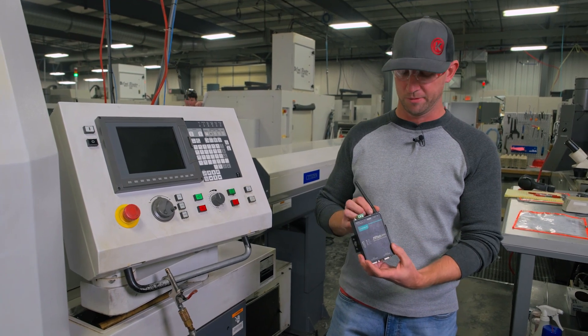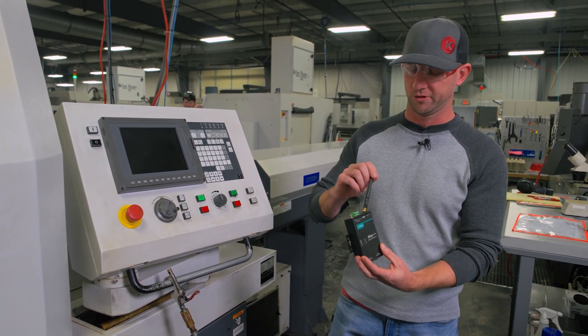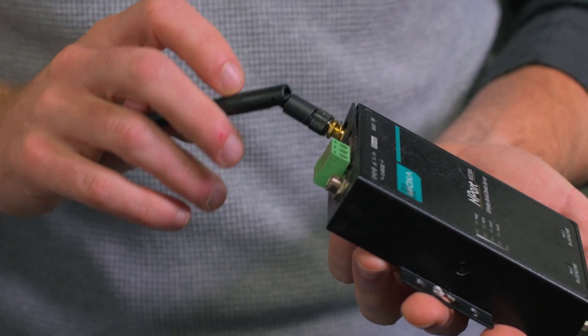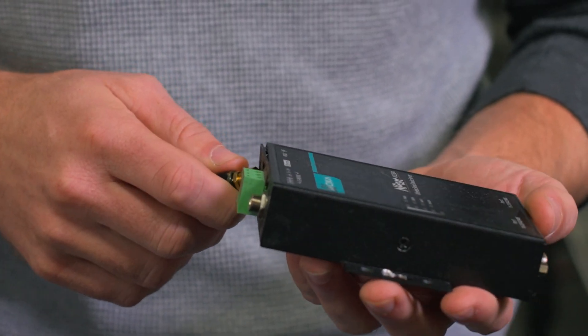It's great for drawing heat out of parts and keeping everything lubricated, but it's horrible for anything made out of plastic. As you can see here, one of our old communication boxes has just fallen into disrepair, mainly from the Swiss oil landing on it and just eating away at it.